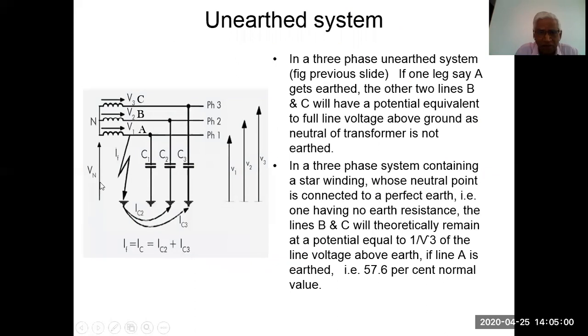The neutral is not earthed, so with respect to the neutral there is some voltage always here, depending on the leakage current from these three capacitors. Now in this case, if there is a fault on line A, these capacitors will try to discharge through this line, and this line is now at ground potential. So VB and VC with respect to the ground will be the full voltage. That is, the line to line voltage will appear between phase 2 and ground, and phase 3 and ground. Between phase 1 and the ground it is zero voltage.